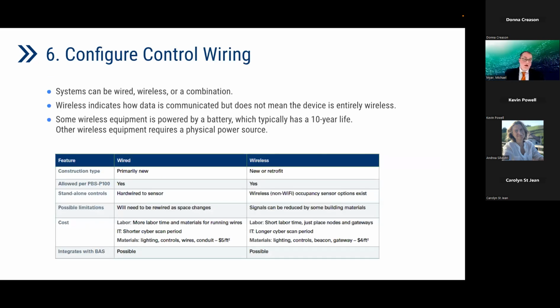Configure wiring. So you're going to go through and figure out all the types of controls you have, then talk about all the zoning you might consider, and finally think about whether it's going to be wired, wireless, or a combination of the two. You may treat this as an iterative process - deciding early if it needs to be wired will affect certain choices; if not, you'll think through all those things. One thing to consider with wireless communication devices, depending on how they work, if they're standalone, they may need battery power, and you may have a limited life of 10 years or less for that battery device. So you need to think about the whole life cycle cost as you consider wired versus wireless.